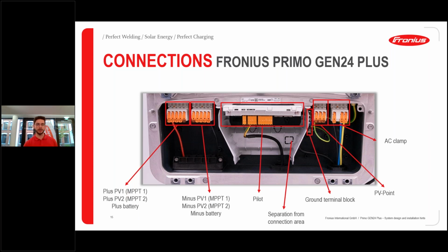And we can see here the 2 MPP trackers. Both of them have 2 inputs, as we can see here. So MPP tracker 1 has 2 plus and 2 minus, and also the second MPP tracker. And I'm not sure how well you can see it, but in the black underlayment, we can see here a battery connection, also for plus and minus. So this is where we can directly connect our DC coupled battery. So this is the DC side on the left side.